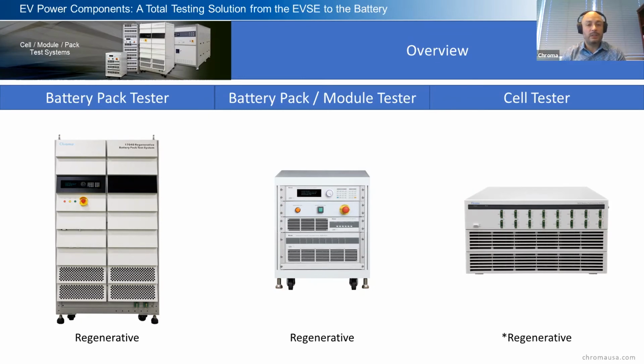I have an asterisk on the cell tester. You don't want a regen design on a low power cell. If we're talking about 50 or 100 watts, even with 16 channels that's only 160 watts to put back onto the grid. It doesn't necessarily help you, and it just increases the cost of the equipment.